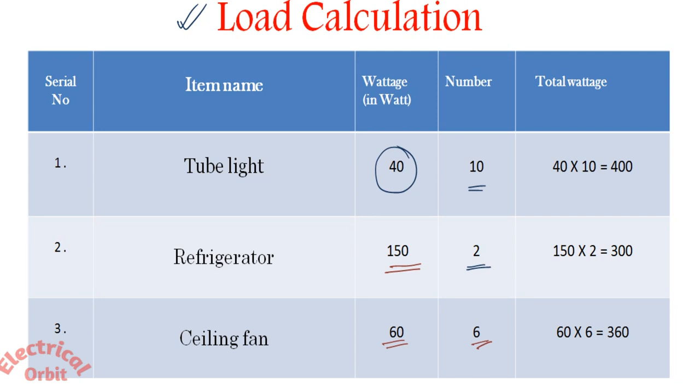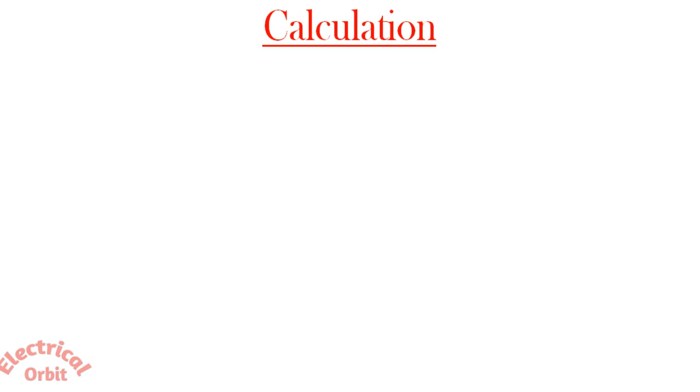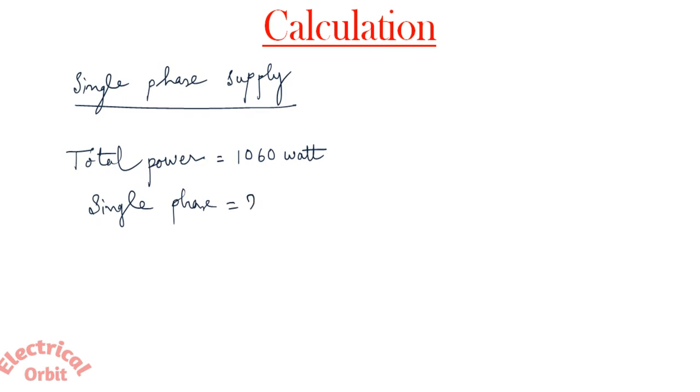Next we have two refrigerators which is 150 watt each and 60 watt rating 6 ceiling fans. So the total number of items here is 18 and their total wattage is 1060 watt. Now first we assume that all these loads are connected with single phase supply. So our total power is 1060 watt, single phase voltage is 230 volt.